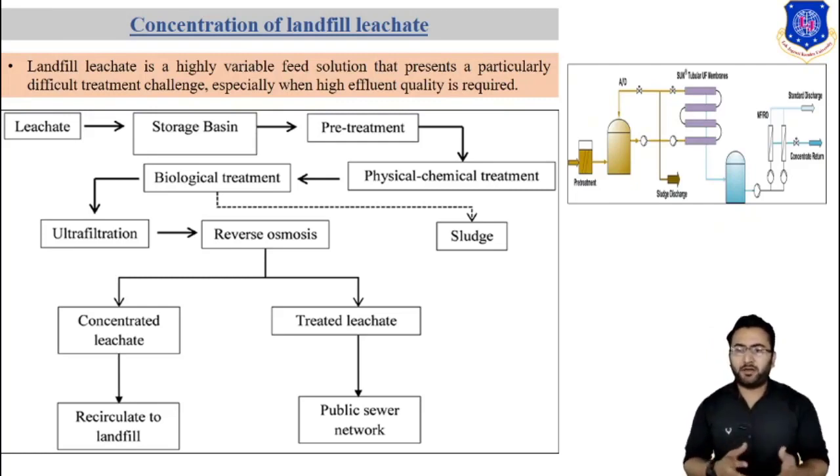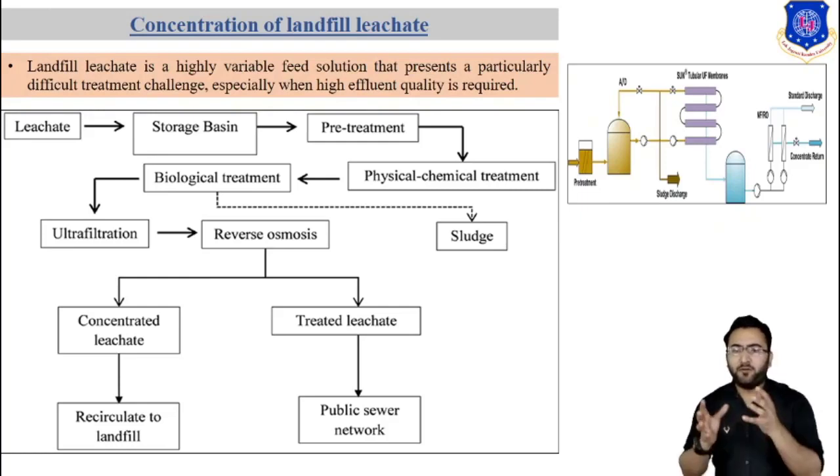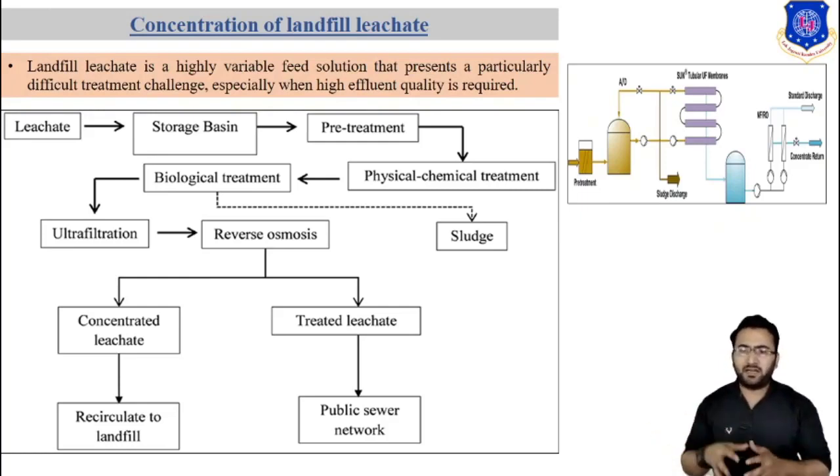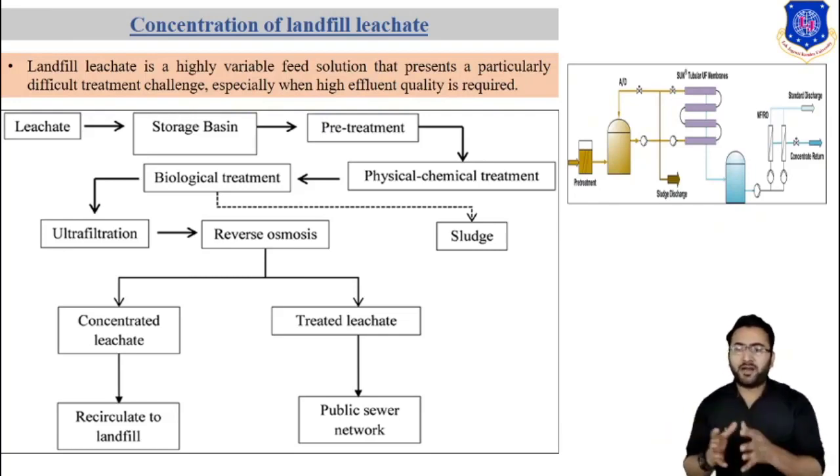Two commercially available treatment processes that are able to efficiently remove TDS from wastewater are mechanical evaporation, such as vapor compression, vertical tube falling film, horizontal tube spray film, and forced circulation, and second, a membrane separation process. A comprehensive evaluation of vapor compression, mechanical evaporation, and reverse osmosis shows that reverse osmosis can be very effective in treating landfill leachate concentration.